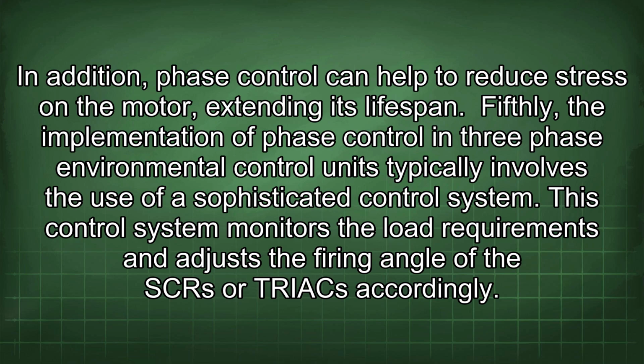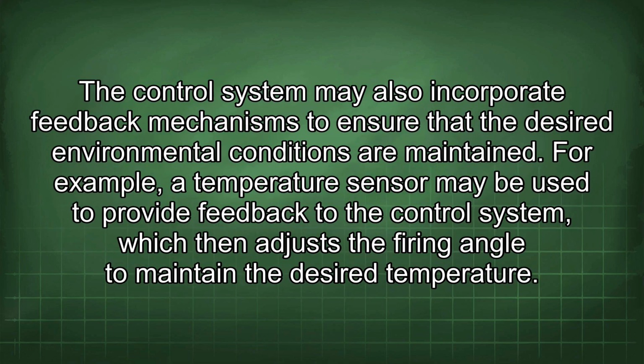Fifthly, the implementation of phase control in three-phase environmental control units typically involves the use of a sophisticated control system. This control system monitors the load requirements and adjusts the firing angle of the SCR or triacs accordingly. The control system may also incorporate feedback mechanisms to ensure that the desired environmental conditions are maintained. For example, a temperature sensor may be used to provide feedback to the control system, which then adjusts the firing angle to maintain the desired temperature.